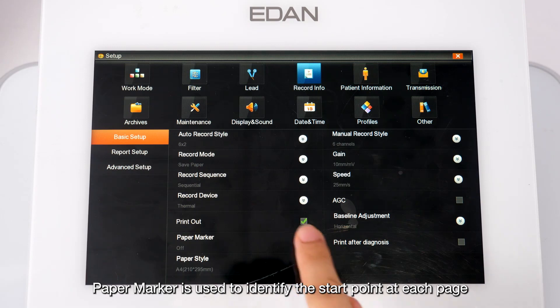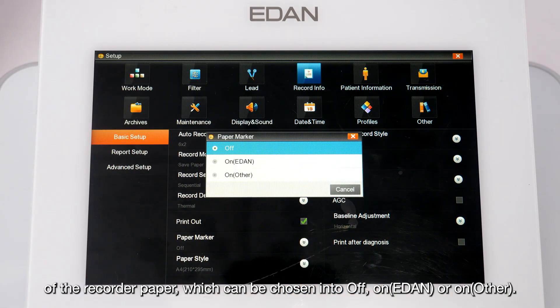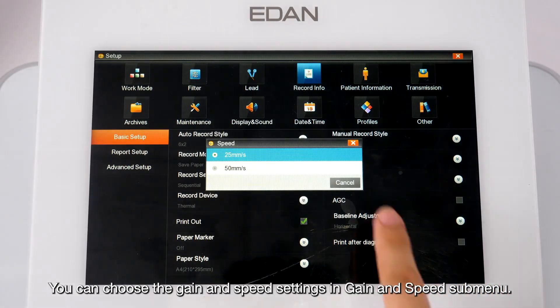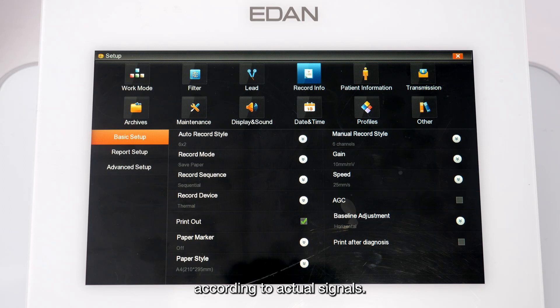Paper Marker identifies the start point on each page of the recorder paper and can be set to Off, On(EDAN), or On(Other). You can choose gain and speed settings in the Gain and Speed submenu. When AGC is selected, the gain is automatically adjusted according to actual signals. Click Baseline Adjustment to set the baselines of ECG waves on the printed report.